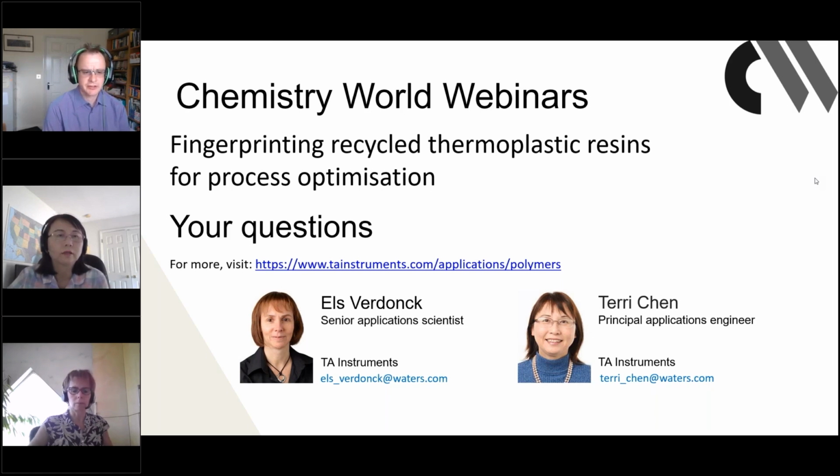Great, thanks very much. Okay, so the next question I think is probably more for Terry. You had a slide about switching to oxidative heating on the DSC, and it says you can use air or oxygen. Does that mean you actually have to connect the DSC up to a pure oxygen supply, or does it just use air as the carrier for the oxygen?